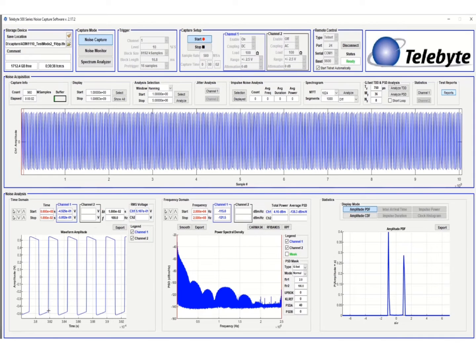The output droop test takes a 0 crossing, looks at the voltage 133 nanoseconds later, and then looks at another voltage value 800 nanoseconds from that crossing. We want this voltage to be less than 25%.